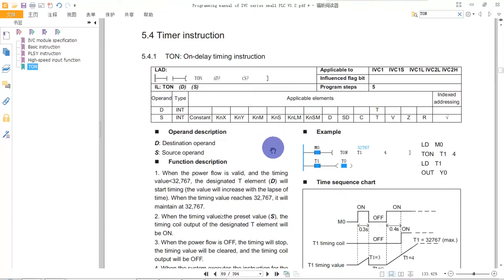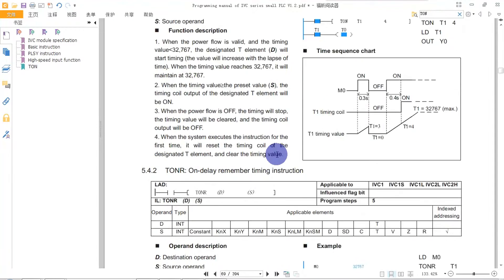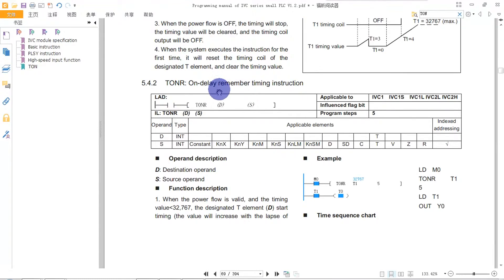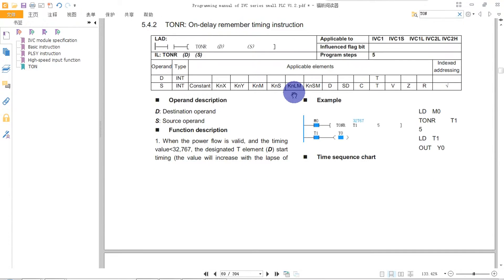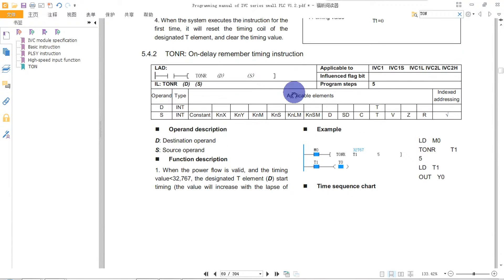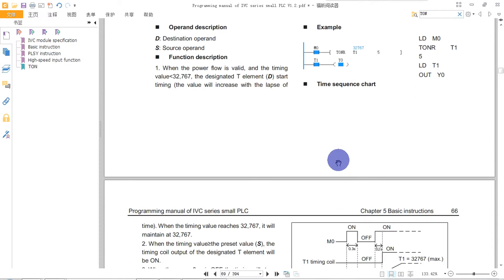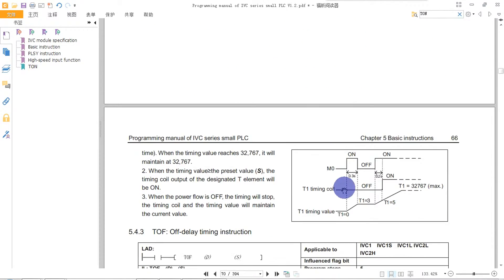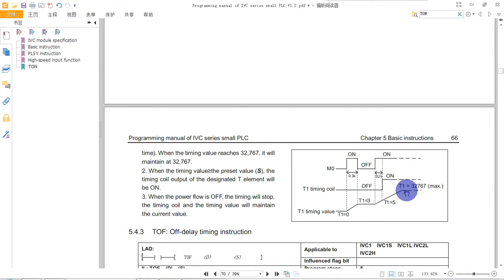Looking at the TONR, the On-Delay Retentive Timer instruction — this means it will record the accumulated time. If the timer input turns off before the preset time is reached, it will remember the elapsed time until the input comes on again, at which point the timer will continue until it reaches its target.